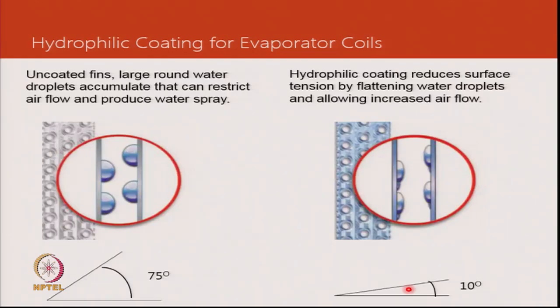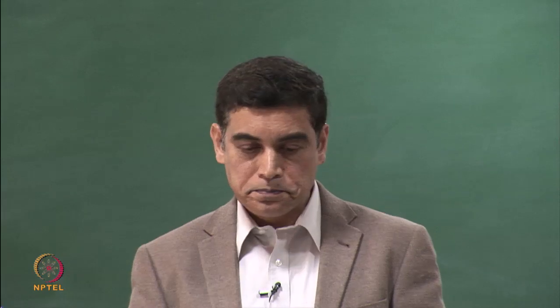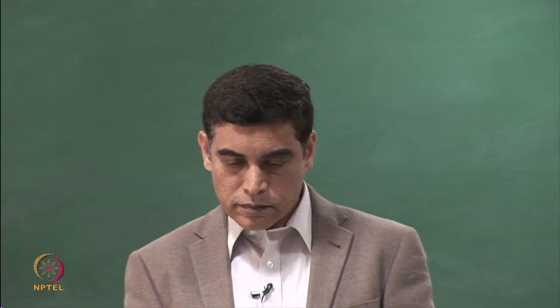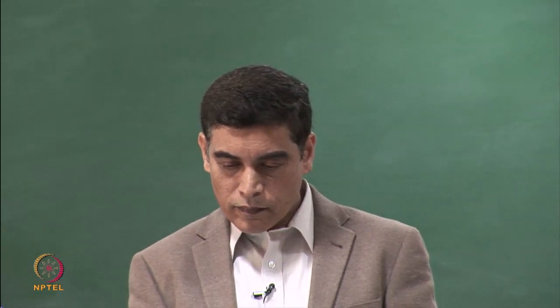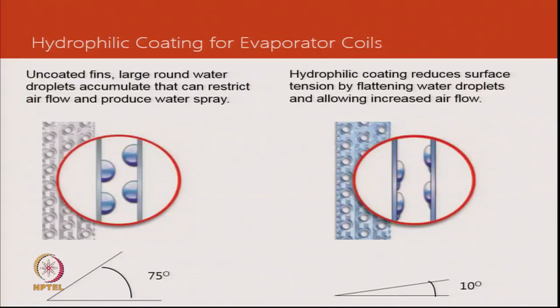So here is the angle of contact. Because the surface tension changes, so the angle of contact changes from 75 degrees to 10 degrees, and this leads to better flow of condensate into the drain pan. This becomes handy when there is a lot of high air velocity in certain parts of the evaporator.